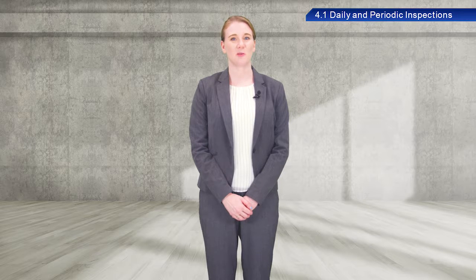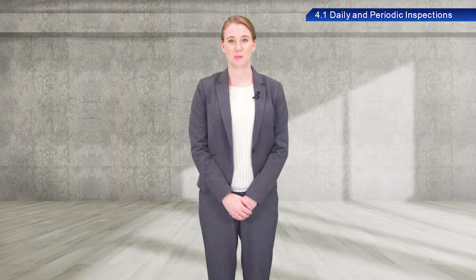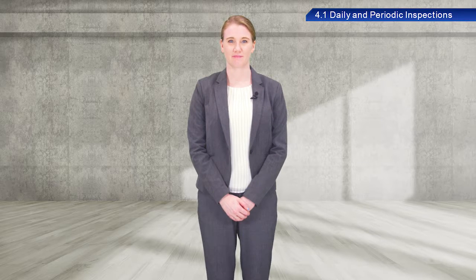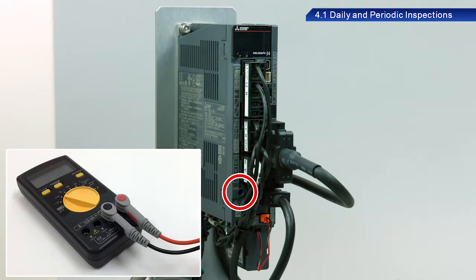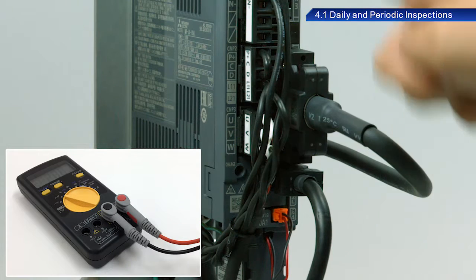Let's now go over the procedure to replace the battery. To prevent electric shock, wait at least 15 minutes after turning off the power to the main circuit and check that the charge indicator lamp is turned off before replacing batteries.